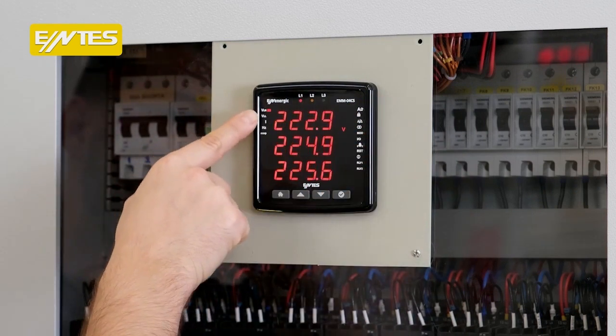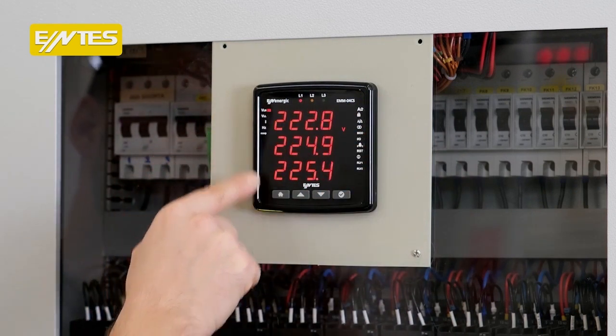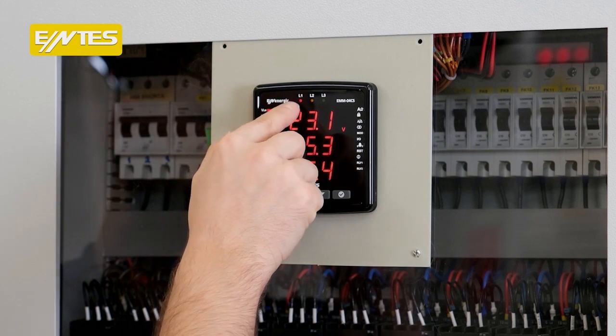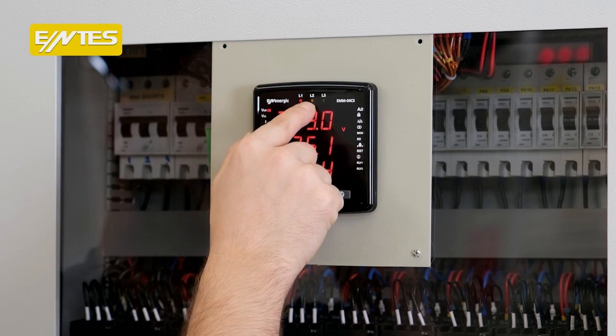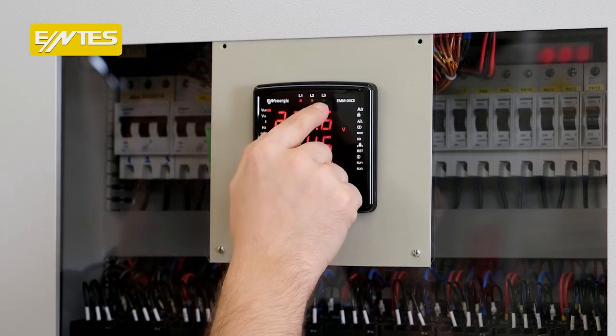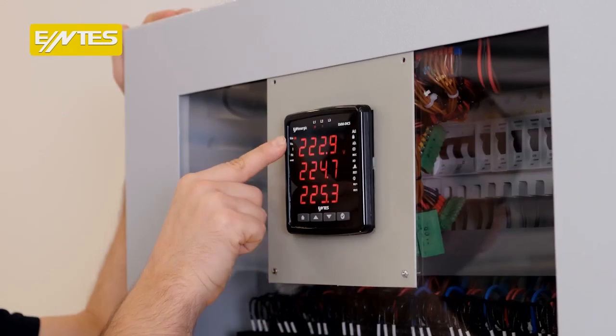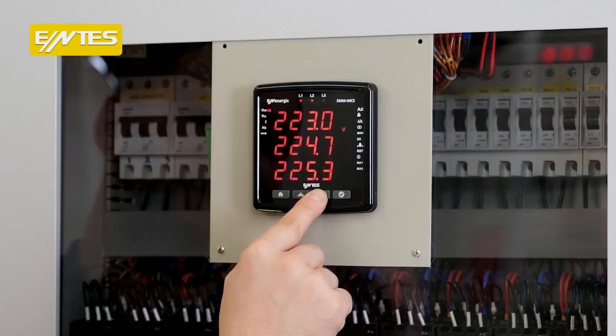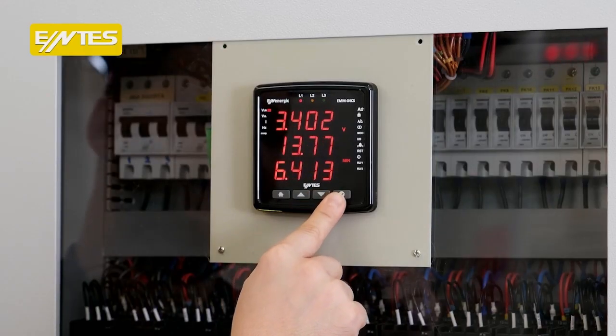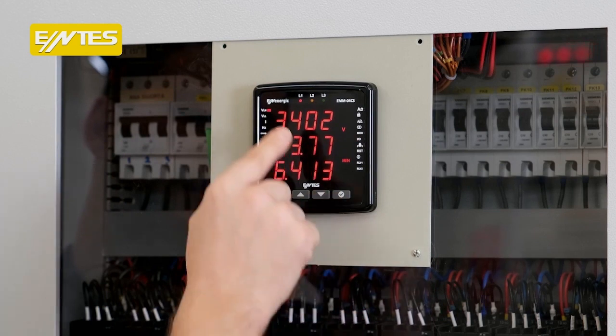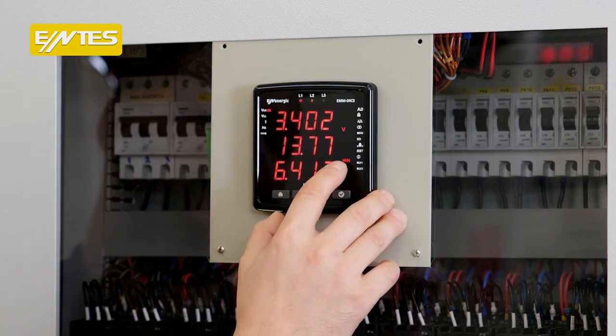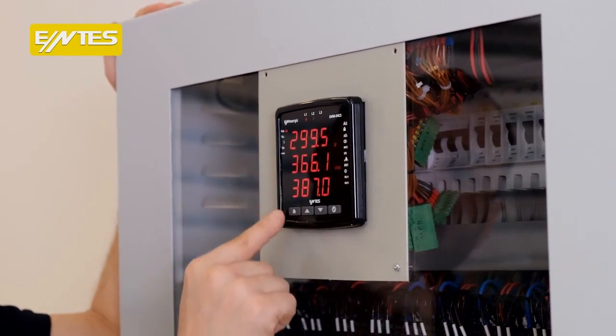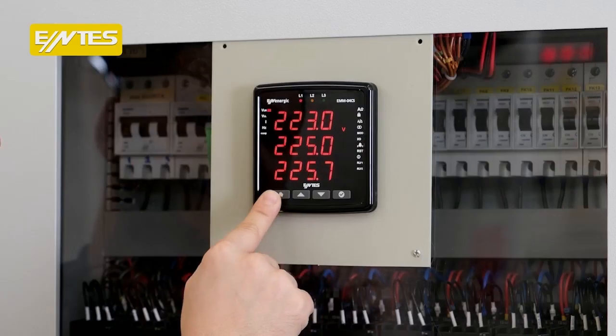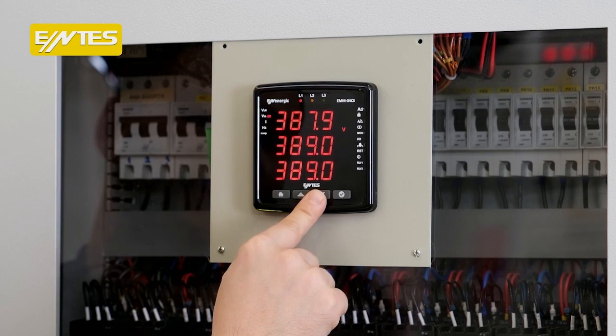Now our voltage screen welcomed us. The measurement screen appeared. Look, here is the red LED indicating phase L1, the yellow LED phase L2, and the green LED phase L3. The phase measurement parameter is chosen at this location. When we press the OK button here and then the down button, the phase-neutral measurement shows the minimum and maximum measured voltage values. We press the home button, we press the down button.